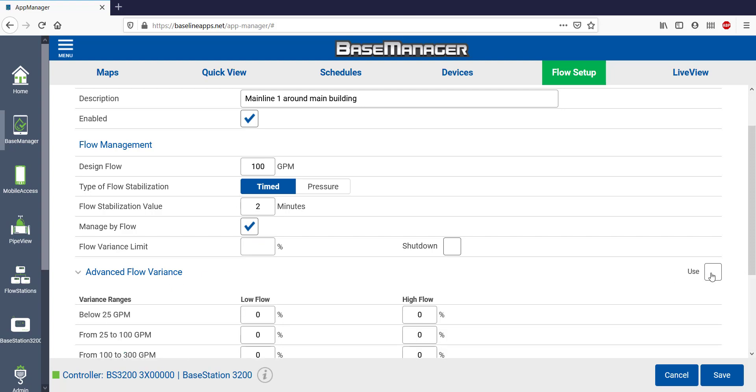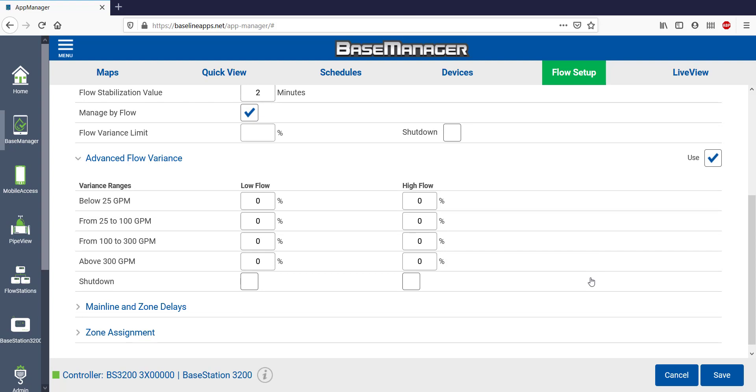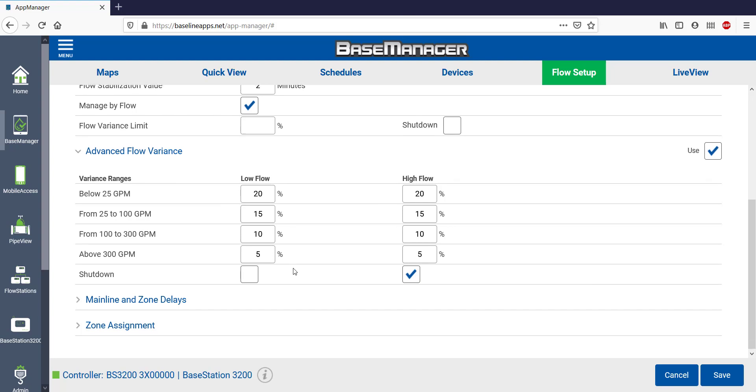A useful setting is Advanced Flow Variance. If I select Use on the right-hand side, it will ignore the above flow variance settings. Now I get the option of adding a range of flows based on the expected flow. I've decided for flows 300 GPM and above, I'll tolerate only a 5% variance. For flows between 100 and 300 GPM, I'll tolerate a 10% variance, all the way down to flows 25 GPM or less, where I'll tolerate a 20% variance. You may need to experiment to find the right settings, but if you have a wide range of flows, this is very helpful. I can also shut down for high flows but not shut down for low flows — just get alerts. There are times when getting some water applied is better than shutting down and getting no water.